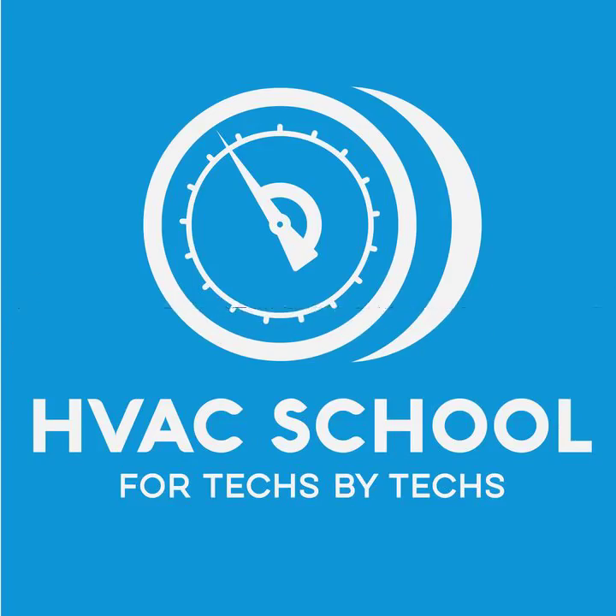So like let's say I diagnose a transformer, I check the voltage coming into it, the potential, and I've got 240 volts coming into it, and I don't have 24 volts coming out of it directly at the transformer. I'm going to pull it out, and once I get it out, I want to see, is the primary open or is the secondary open?